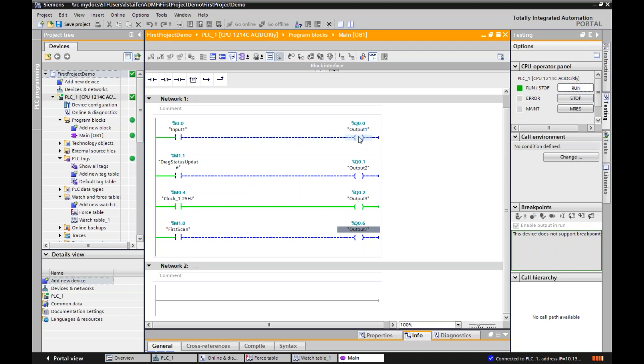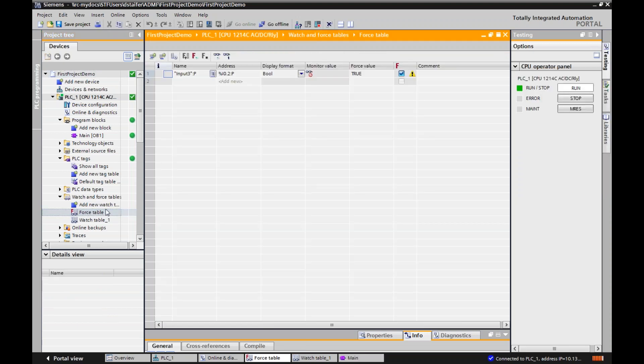Now let's talk about forcing. Forcing would be a good thing — but you should use this only if you're needing to do maintenance, if you need to turn off an output to remove a piece of malfunctioning equipment and you can't get the conditions met. This is only to be used when you are in maintenance. Please do not utilize this to fix an issue. It's been known before in other applications that people will just force on an input to make something happen, and that's not good because when you try to change things, that will create issues down the line. So only if you put in a force, remove it once you're done.